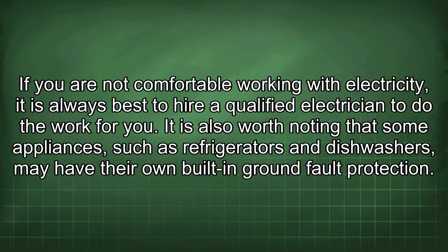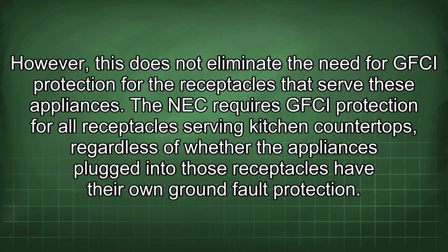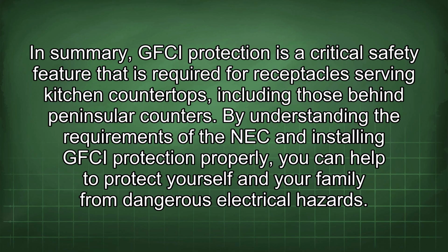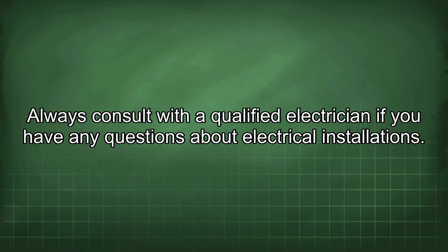It is also worth noting that some appliances, such as refrigerators and dishwashers, may have their own built-in ground fault protection. However, this does not eliminate the need for GFCI protection for the receptacles that serve these appliances. The NEC requires GFCI protection for all receptacles serving kitchen countertops, regardless of whether the appliances plugged into those receptacles have their own ground fault protection. In summary, GFCI protection is a critical safety feature that is required for receptacles serving kitchen countertops, including those behind Peninsular counters. By understanding the requirements of the NEC and installing GFCI protection properly, you can help to protect yourself and your family from dangerous electrical hazards. Always consult with a qualified electrician if you have any questions about electrical installations.